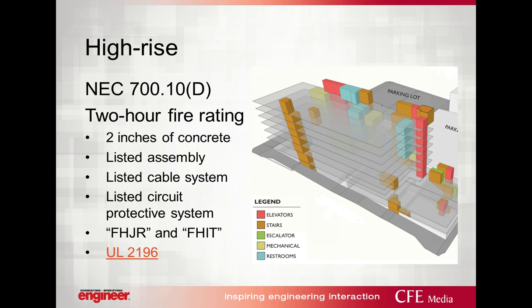Now, if you're curious a little bit about what fire systems you can use, UL 2196 is the standard for the fire test for circuit integrity of fire-resistive power cables. It's very long, and it uses a couple of acronyms that don't seem to match up to the definitions. For example, fire-resistive cables are FHJR, and they're intended as the installation of specified individual electric circuit integrity systems, which is abbreviated FHIT. Normally in our industry, abbreviations match the words that are associated with them. Just understand that here they do not.